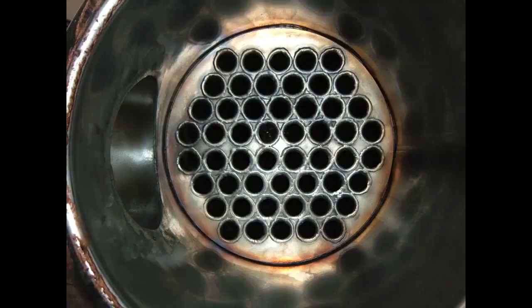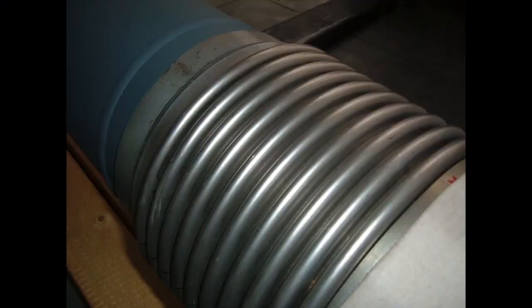You need to exercise caution as this type of construction necessitates specific safety measures. For example, all the tubes are welded and chamfered on the headers. It is not enough to just tighten the fittings because thermal expansions could lead to a detachment of the pipe from the head and therefore leaks. An expansion joint is typically installed on the mantle.